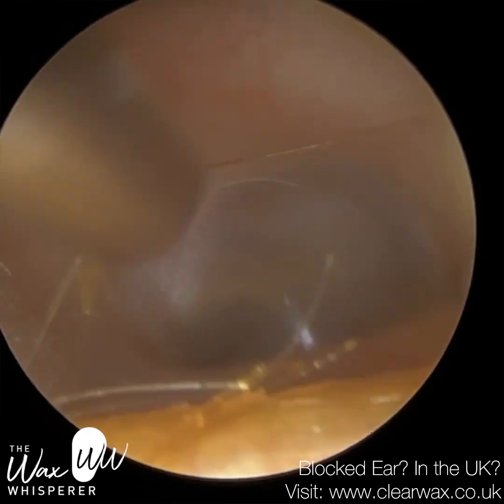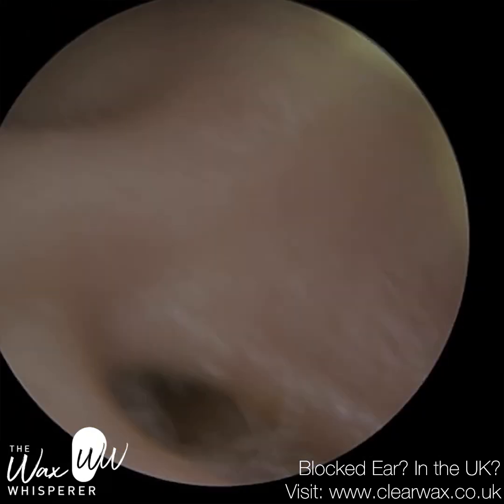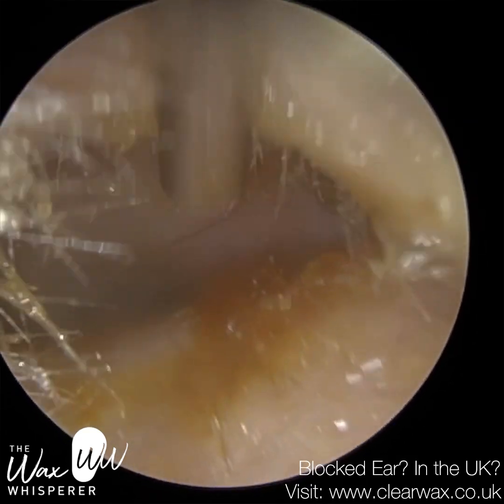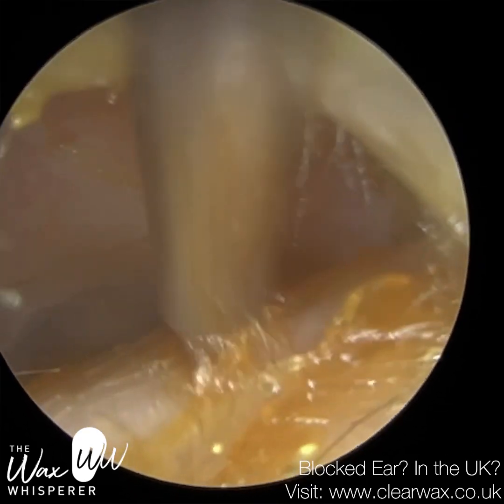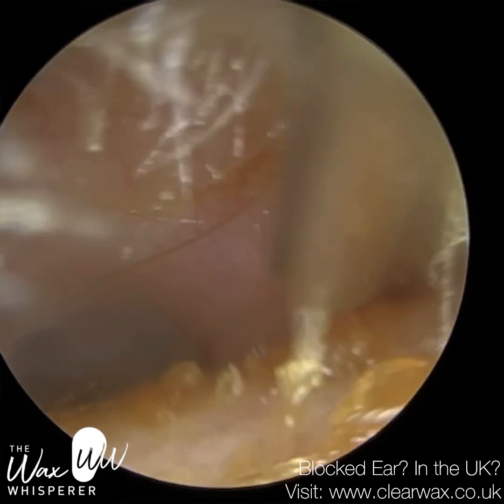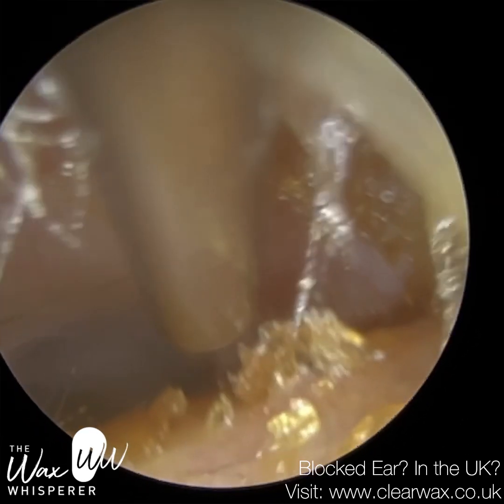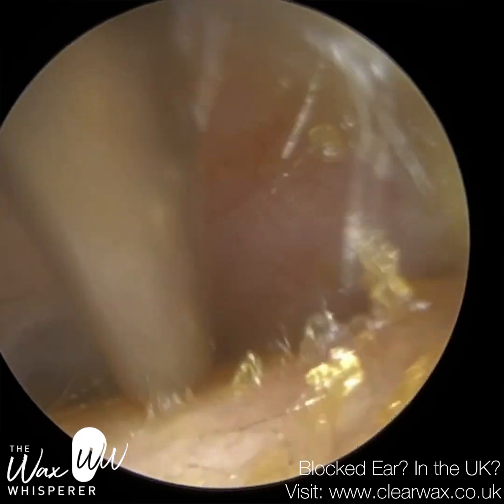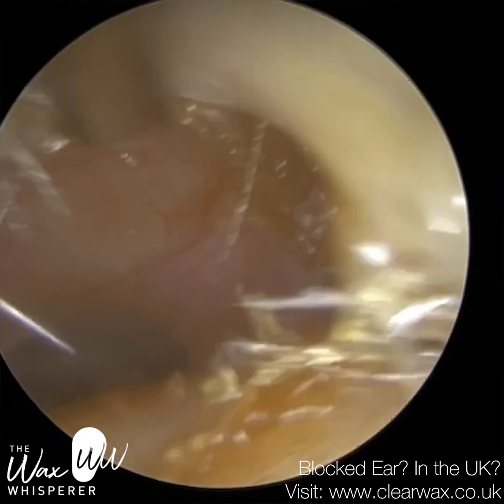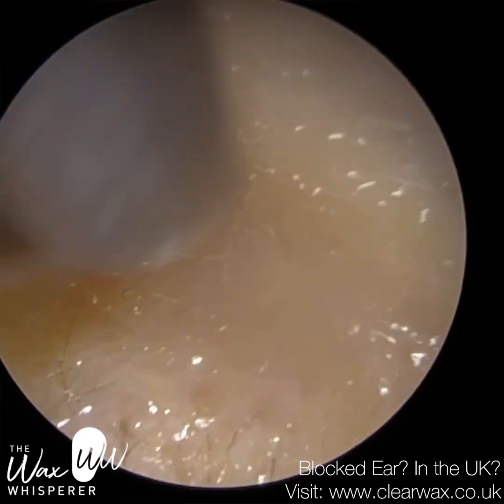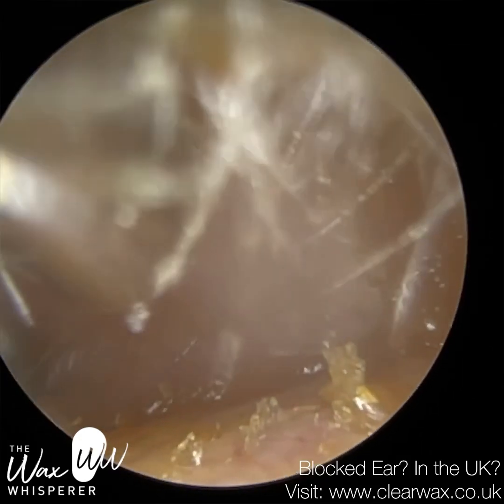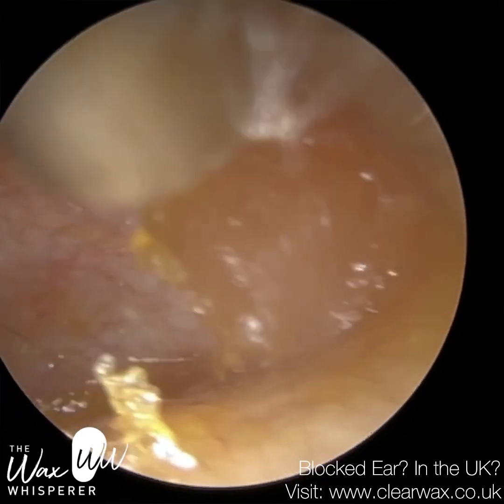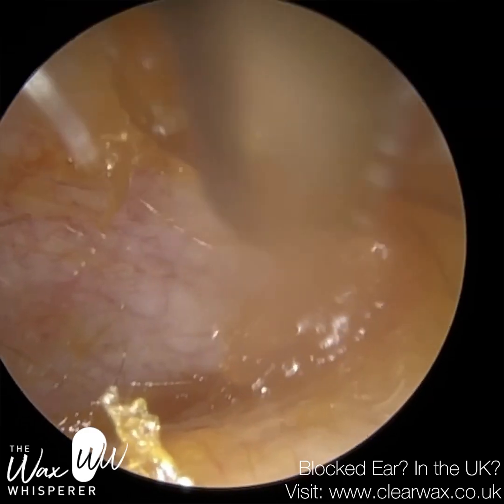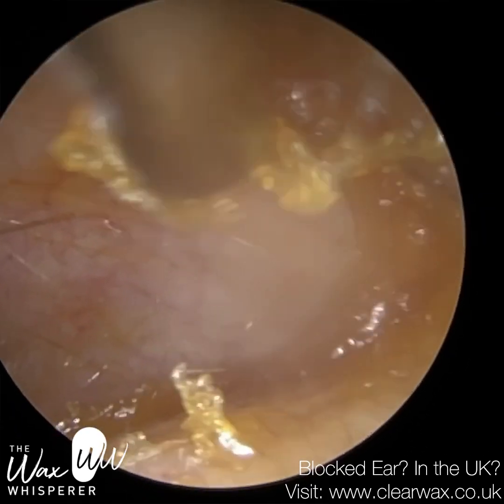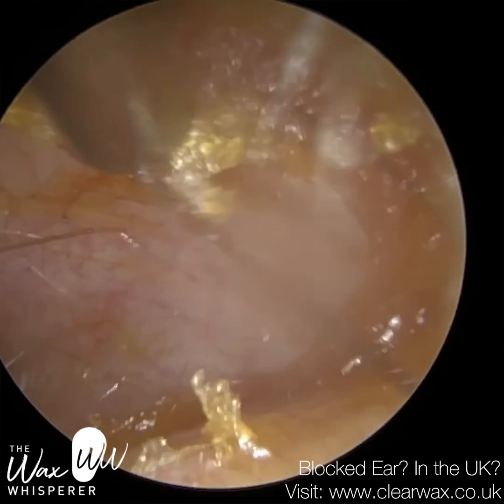Now, I do know of some people that actually clean their own suction tubes, and you shouldn't be doing that, guys. You have to abide by the manufacturer's instructions, and with the suction probes, they're clearly labelled "do not reuse," single use, and these guidelines are put in place by the regulatory bodies as well, especially for suction tubes, because they're class 2A medical devices, so they're not class 1. The suction tubes are a bit more high risk, so you have to have an authorised body to notify and go through all your legislation, all your regulation and documentation, and so it's a bit naughty because you don't want to cross-contaminate.